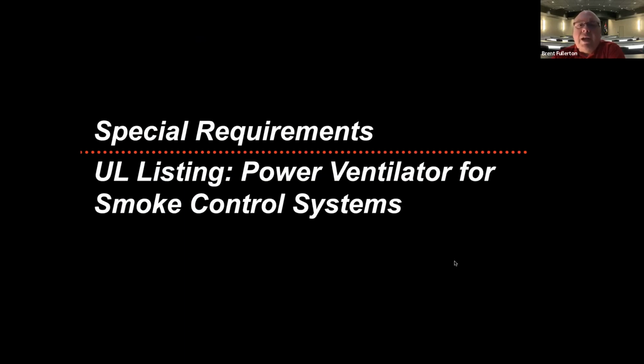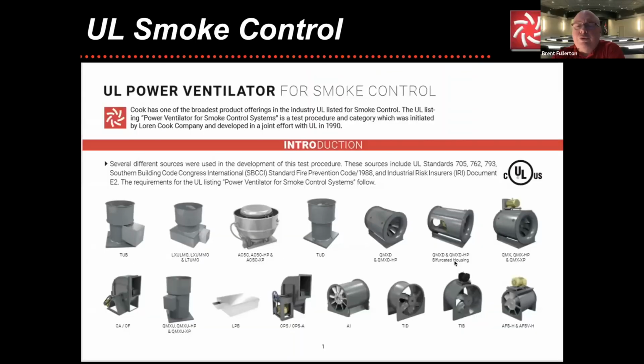Now, there are also some specialty applications that can affect the choices of the style of product and the type of product for these roof-mounted fans, specifically power ventilator for smoke control. Some codes, some building designs require, in case you do have a fire, a method to exhaust the smoke. And there is a specific UL outline and investigation for the product. And with that in mind, that ranges. And here's a simplified outline of some of these different style of products, but some of those roof mounted products, just like as we highlighted, you can see right here, they have that option.